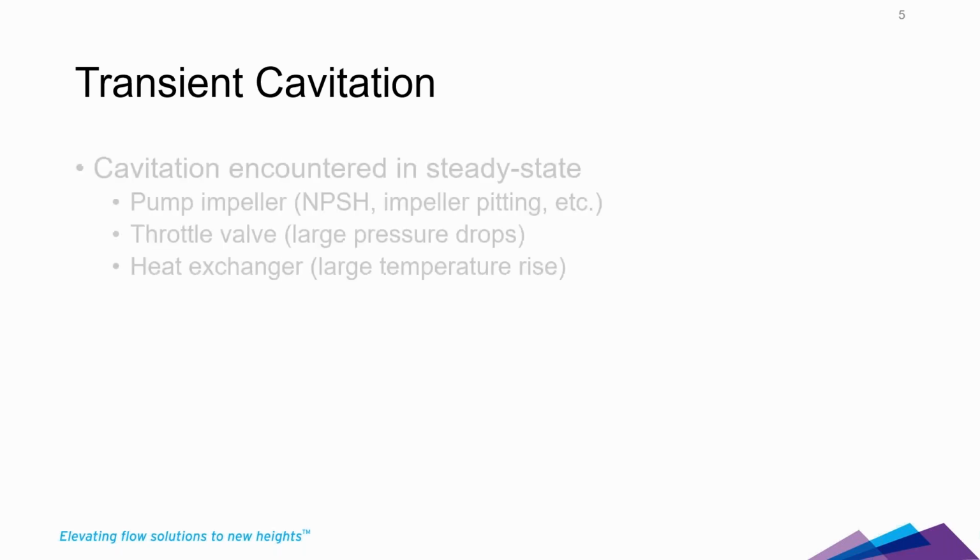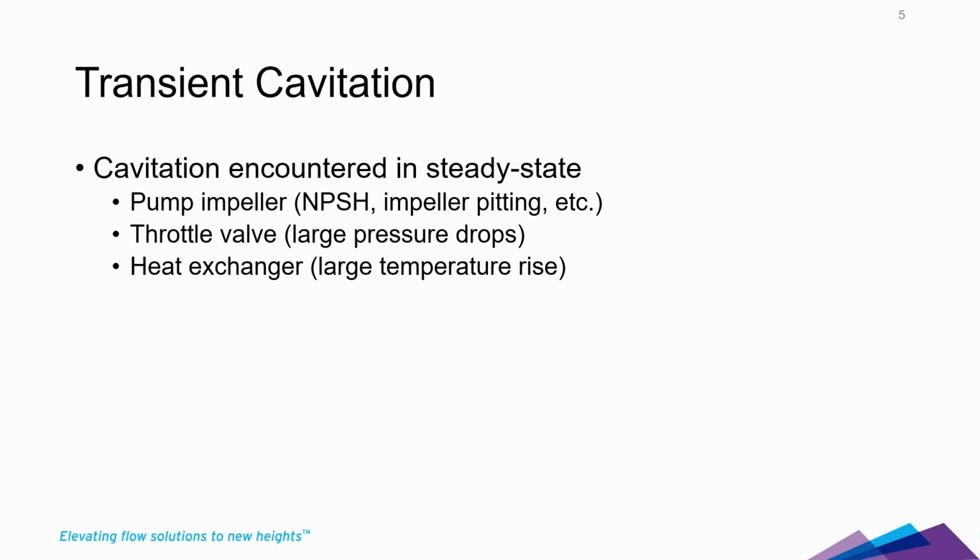Now, a couple of terms that are important here are transient cavitation and the implications of what this sometimes might be meaning. So when we talk about transient cavitation, there's also cavitation that can be happening in typical steady state operation. So this is where you don't have a particular event like a valve closure or a pump trip that causes the cavitation. This is something where your cavitation is much more sustained over a long period of time potentially.